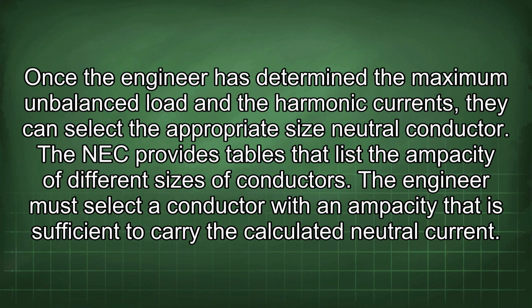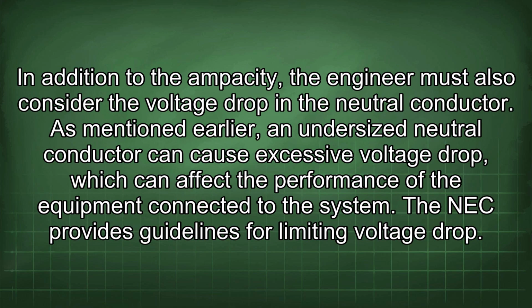Once the engineer has determined the maximum unbalanced load and the harmonic currents, they can select the appropriate size neutral conductor. The NEC provides tables that list the ampacity of different sizes of conductors. The engineer must select a conductor with an ampacity that is sufficient to carry the calculated neutral current. In addition to the ampacity, the engineer must also consider the voltage drop in the neutral conductor. As mentioned earlier, an undersized neutral conductor can cause excessive voltage drop, which can affect the performance of the equipment connected to the system. The NEC provides guidelines for limiting voltage drop.